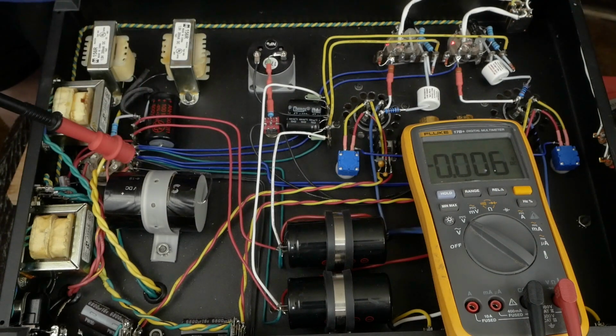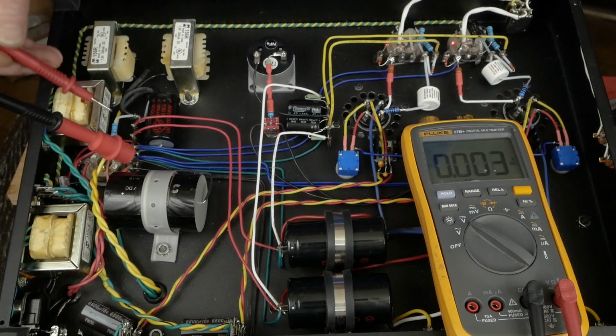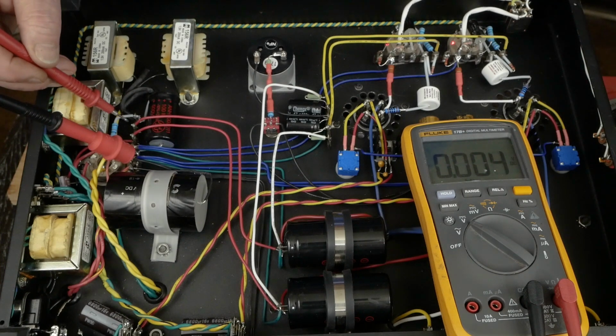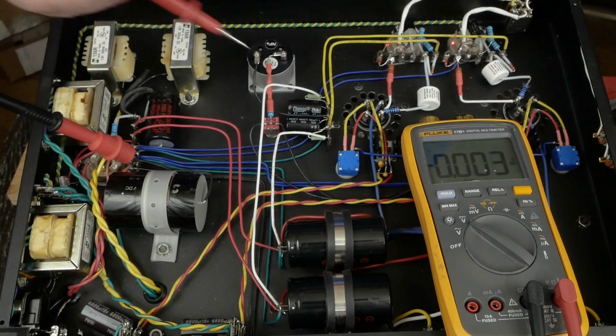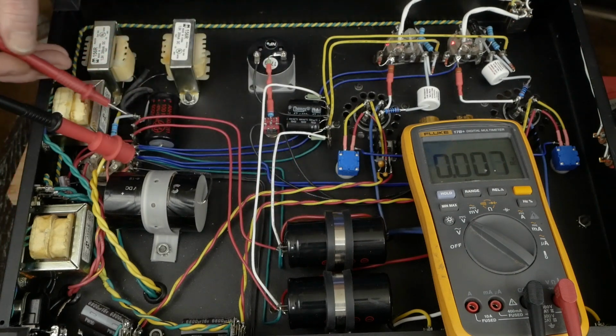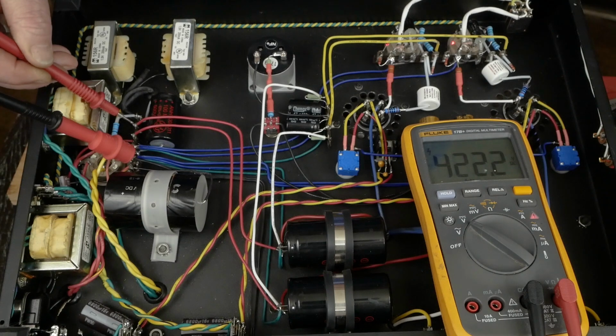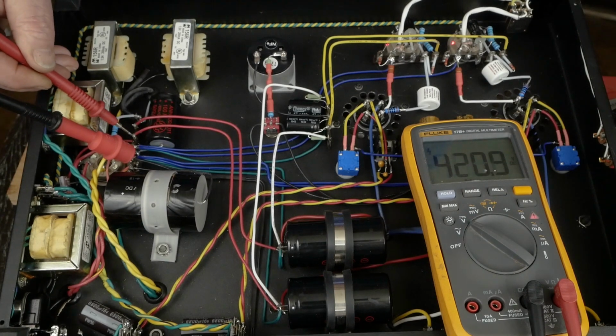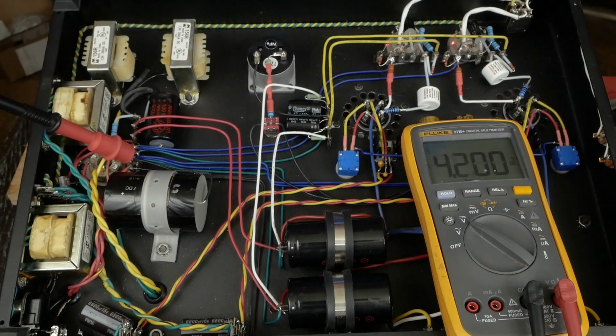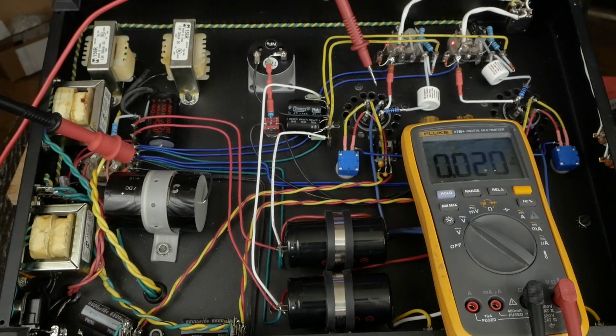So now we're going to start doing our high voltage testing, and I have one hand behind my back while doing this. We're going to check the voltage here coming out of these chokes that is filling up these big storage caps. There's 422 and 420. That all looks good. A little lower voltage than we had out of the other transformer, which I think was closer to 430, but I'm not worried about that.